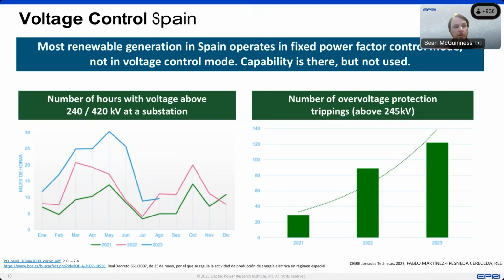As a result of that, you can see from these charts, which Red Electrica have previously published, that the 220 kV and 400 kV grids have, in a number of hours every year in recent years, been operated above their normal operating range and above their normal operating limits. You can see here it ranges from 5 hours up to 30 hours per month where they're actually operating at or above their normal operating range. So there are quite some challenges in down regulating the voltage in Spain in general.